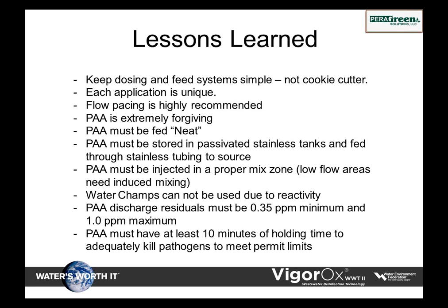So what they did is they reverted to the online monitor we have that's in the water. For 2 days, they used that as the controller. Now, there's a differential there. We found out what the difference was, but they used the monitor as a controller and kept in compliance. So again, you can do it. There's a lot of work being done now in online monitors and online analyzers, and they're really moving a lot further than what normally was out there in the market. Next thing, every application is unique. I go and see every single facility before we even attempt to feed.